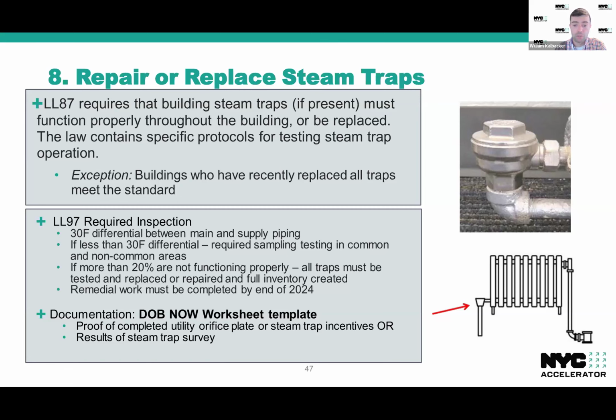And you really need to create a full inventory of all of your traps and all of your test results for documentation purposes. All of this work needs to be done by the end of this year, so it's very important to get on top of this. This is another measure that has a specific worksheet requirement for compliance under the DOB Now system. It's going to either require proof that orifice plates or steam trap incentive documentation is provided, or it's going to require that steam trap survey.